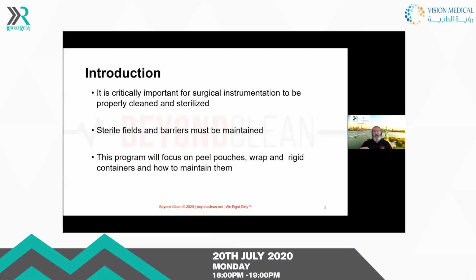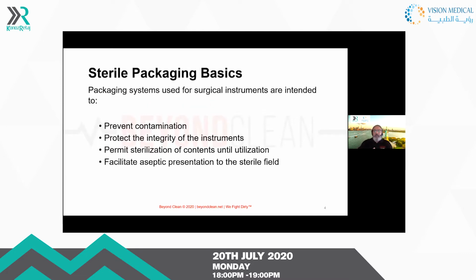And today, our program will focus on peel packs, wraps, the blue wraps, and then rigid containers. Some of you may have seen in the past where we have used even some linens in our sterile packaging, and we don't see that very much here in the US anymore, and I would assume that it's the same in your country as well. So as you think about sterile packaging basics, the systems are used for surgical instruments to, number one, prevent contamination during use. We always would like to protect the integrity of the instrumentation. Certainly we want to permit sterilization until the instrumentation is used. And then when they get to the operating room, whatever packaging method you choose, we want to make sure that it will facilitate the aseptic presentation to the sterile field.